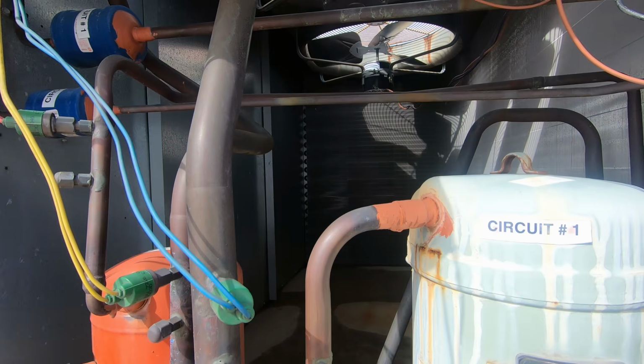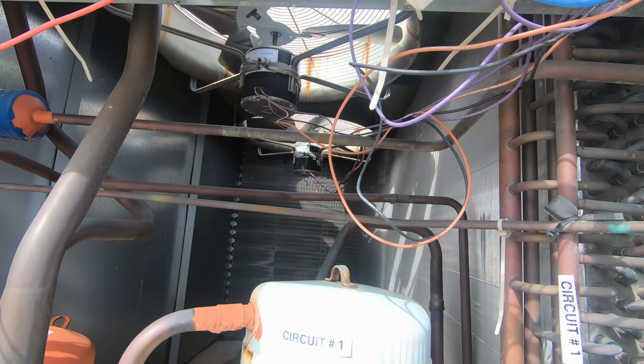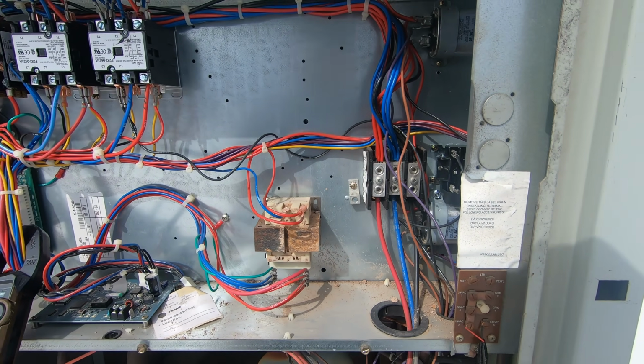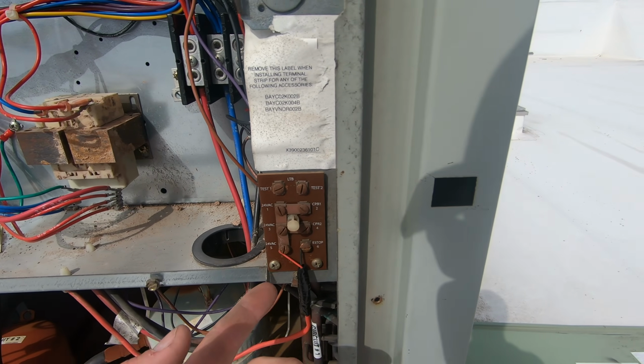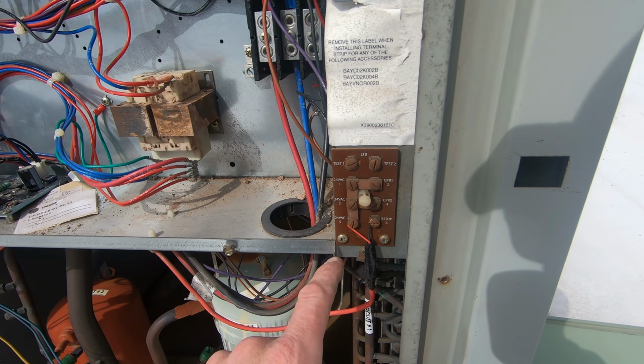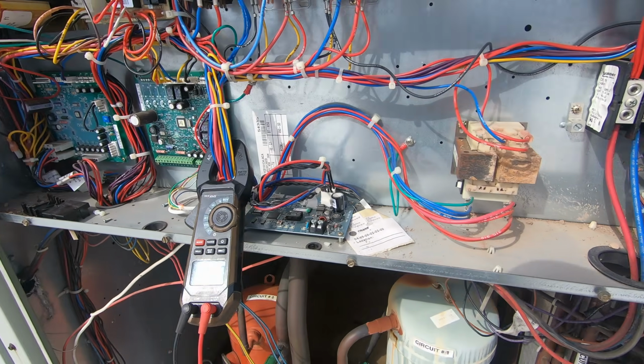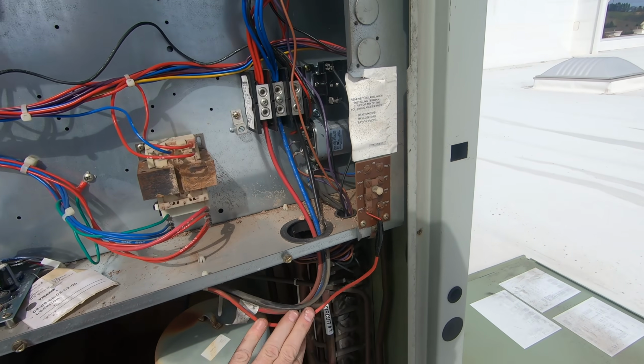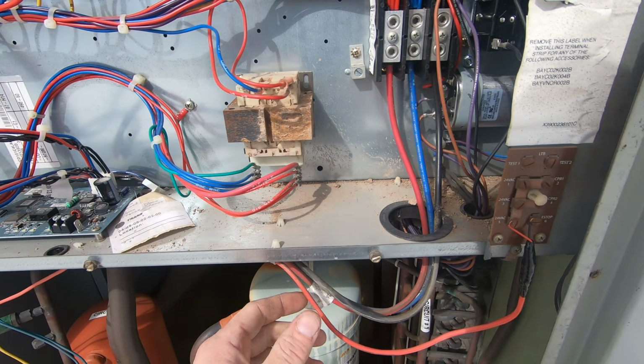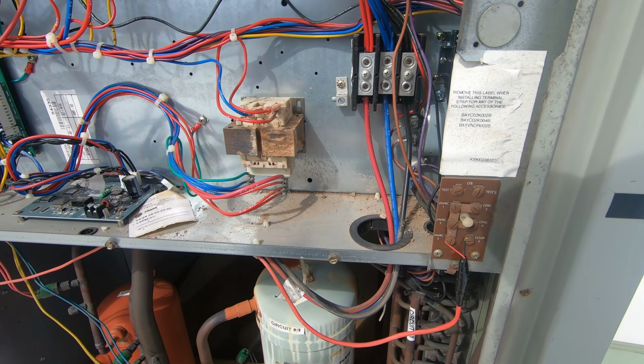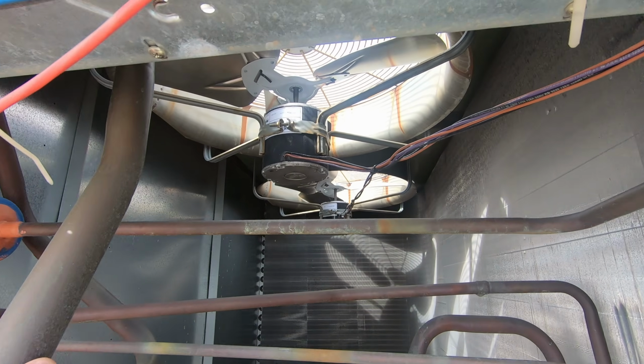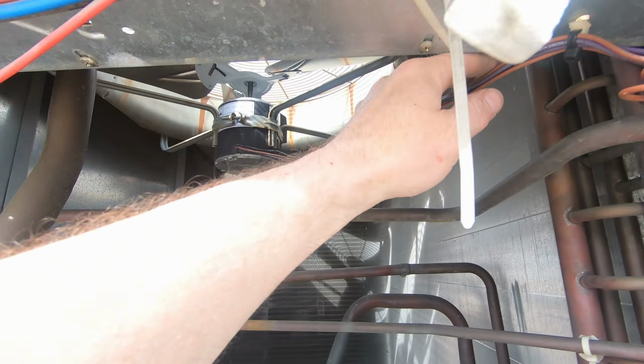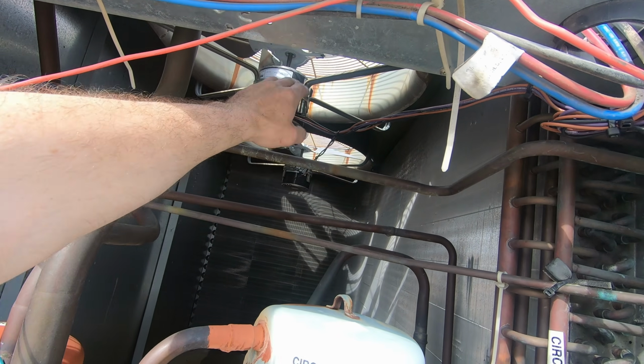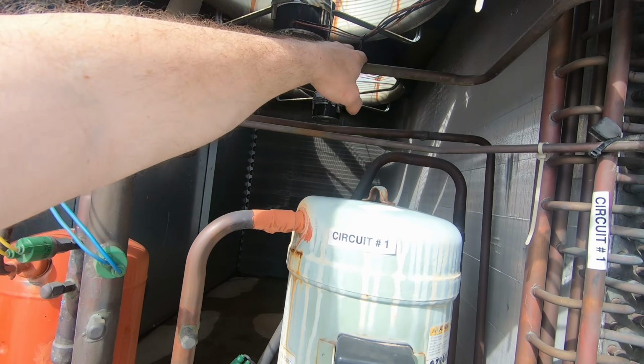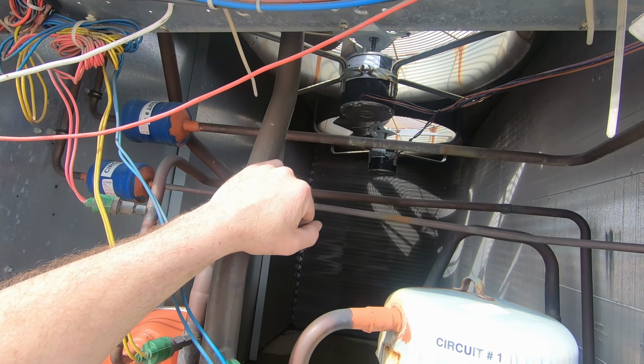Yeah, we had a 24 volt short to ground, and right off the bat I found this wire, 24 volts, arcing, touching right there. So I've got this 24 volt wire to the smoke detector repaired. I went ahead and pinned up the wires so they're nice and taut and not drooping and laying on the pipes where they can rub out.